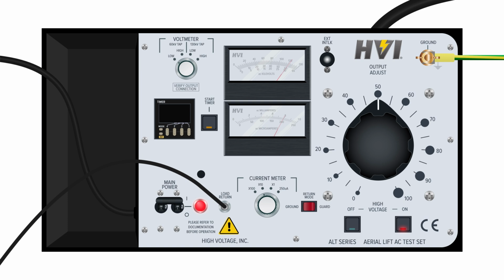When the test duration is complete, turn down the high voltage output to 0. Press the high voltage circuit off button to deactivate high voltage. Double-check that the voltmeter is reading 0. Finally, confirm the high voltage section is grounded, and then disconnect the output lead from the DUT.